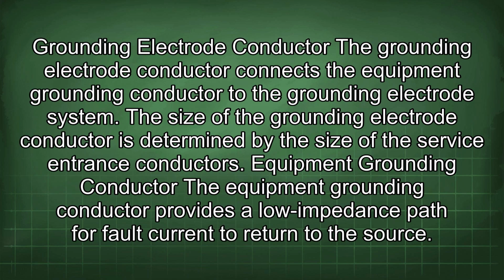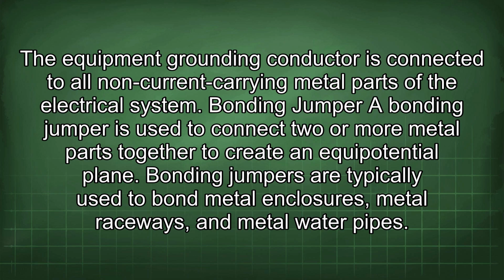Grounding electrode conductor. The grounding electrode conductor connects the equipment grounding conductor to the grounding electrode system. The size of the grounding electrode conductor is determined by the size of the service entrance conductors. Equipment grounding conductor. The equipment grounding conductor provides a low impedance path for fault current to return to the source. The equipment grounding conductor is connected to all non-current carrying metal parts of the electrical system. Bonding jumper. A bonding jumper is used to connect two or more metal parts together to create an equipotential plane. Bonding jumpers are typically used to bond metal enclosures, metal raceways, and metal water pipes.